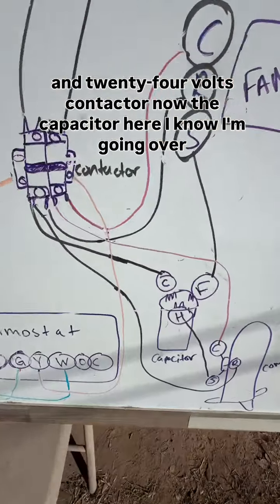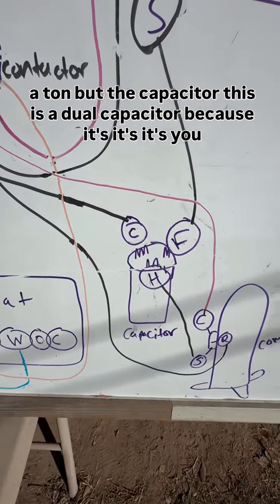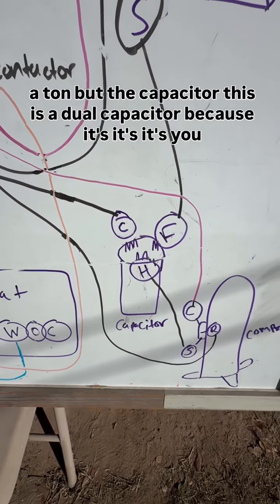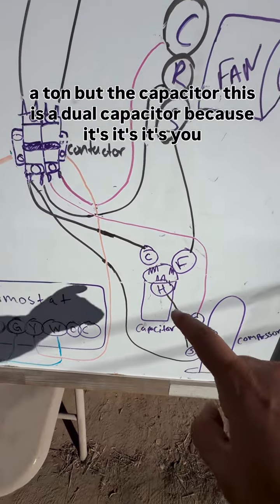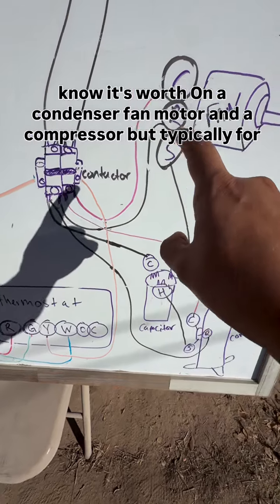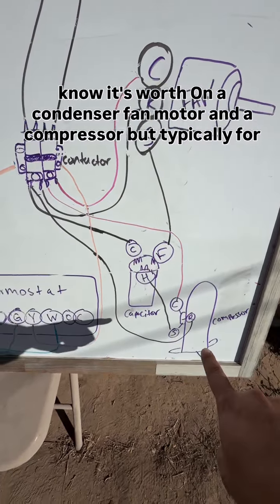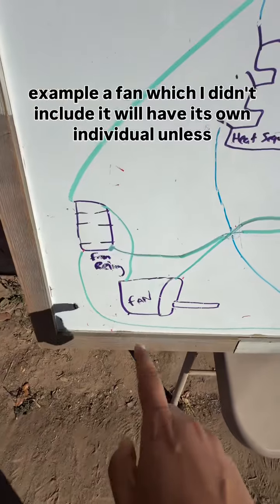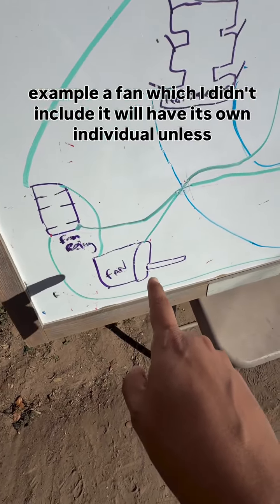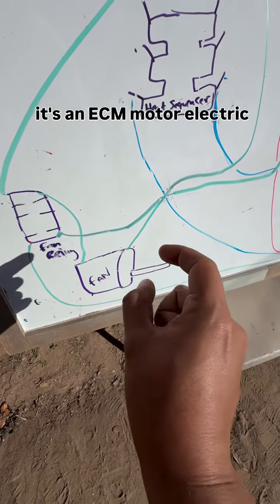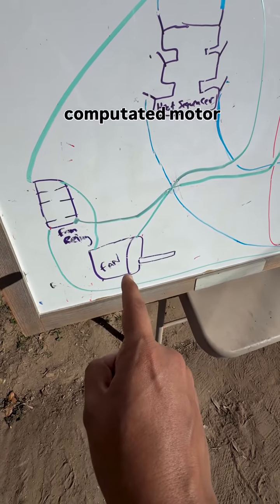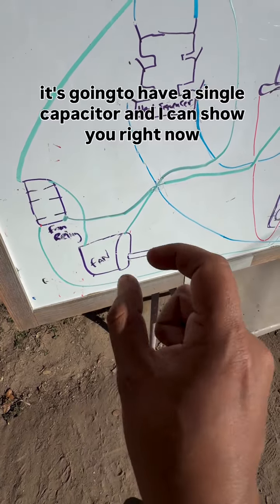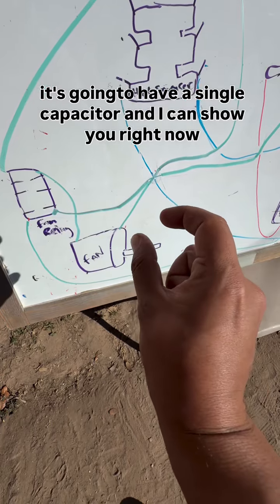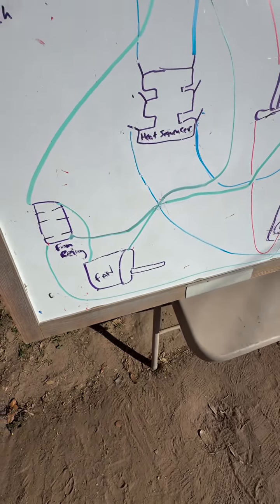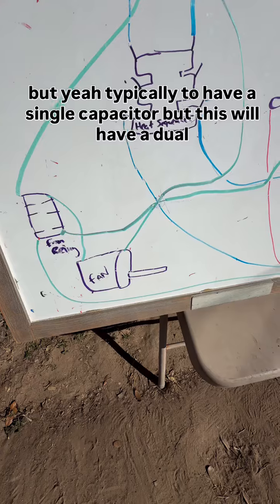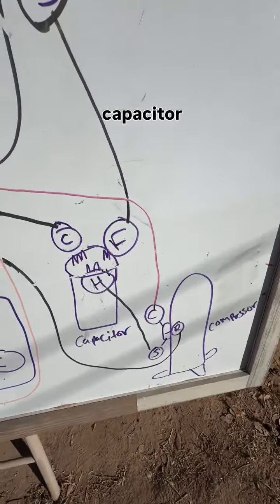Now the capacitor here—I know I'm going over a ton—but this is a dual capacitor because it's working on a condenser fan motor and a compressor. Typically, a fan, which I didn't include, will have its own individual capacitor, unless it's an ECM motor, an electronically commutated motor. I could show you right now, but typically they'll have a single capacitor, while this will have a dual capacitor.